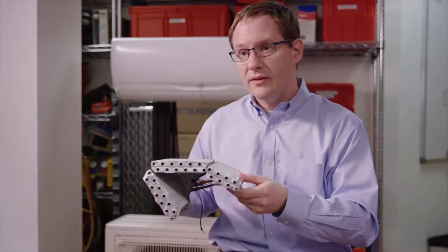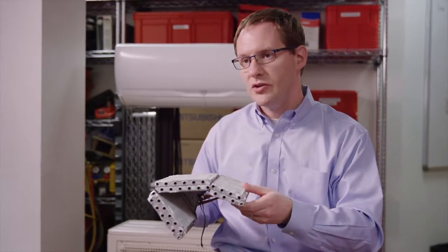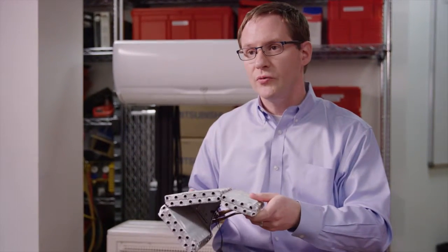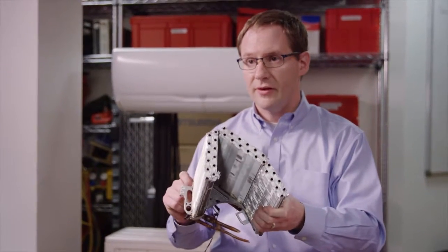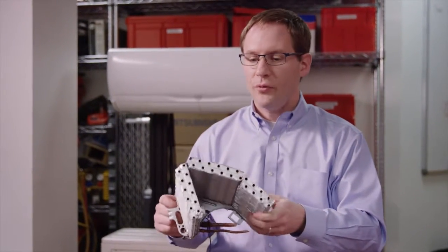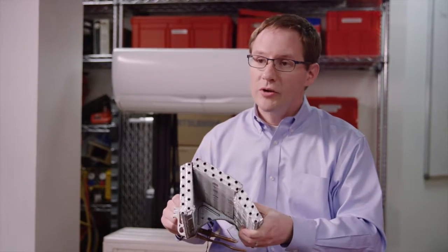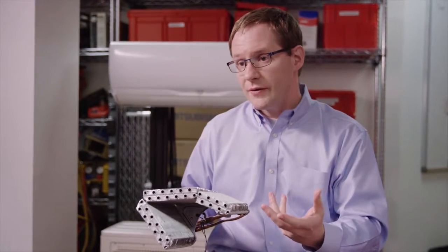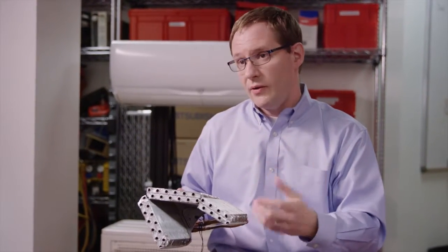But as you try to shrink this, you start to run into fundamental physical limitations for what the heat transfer can be. So we have a number of projects that are trying to really improve the mechanics of exactly what's going on inside these systems, both at a component level and at a system level. So one project that we're working on is looking at how you improve mixing in these channels. Basically, for heat transfer, you really want to have good mixing throughout the channel. But as you shrink these channels, it goes to a flow regime where you don't get a whole lot of mixing, and the performance actually goes down as you try to make them smaller.